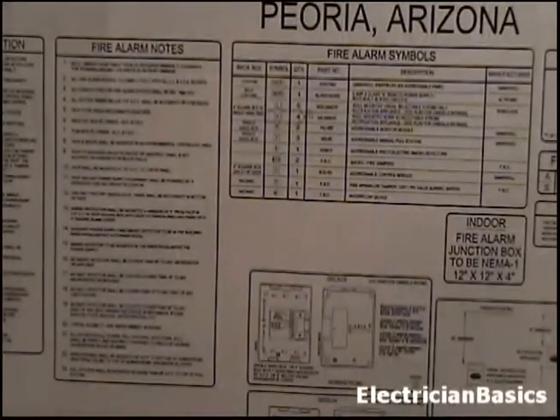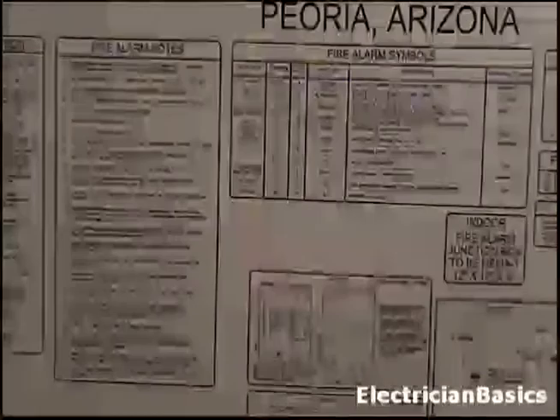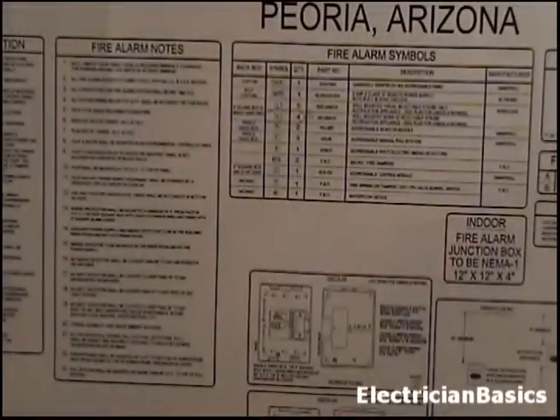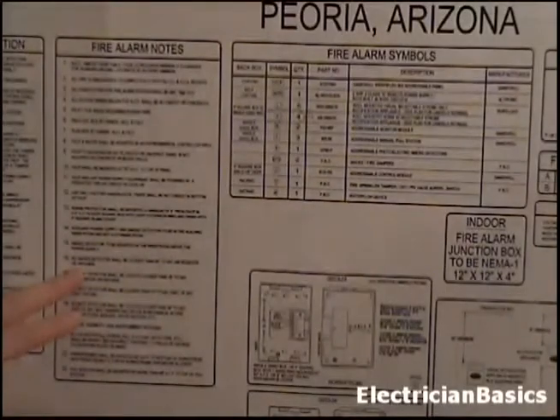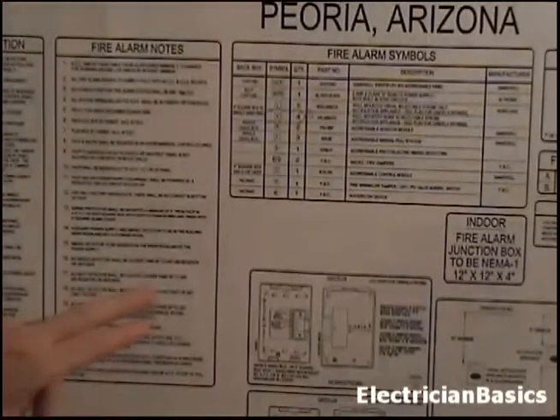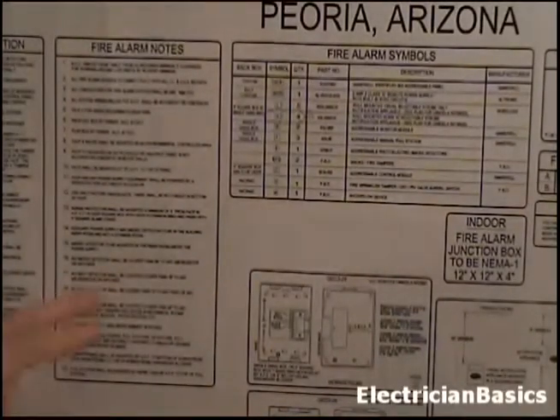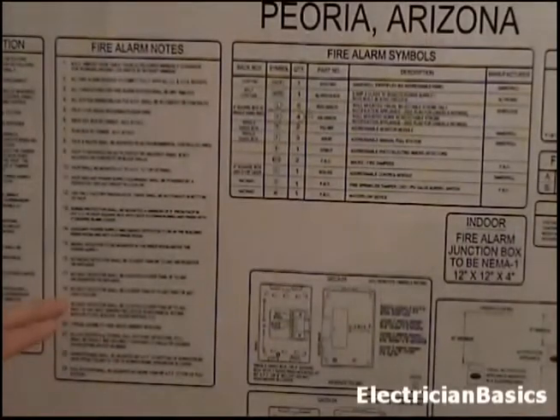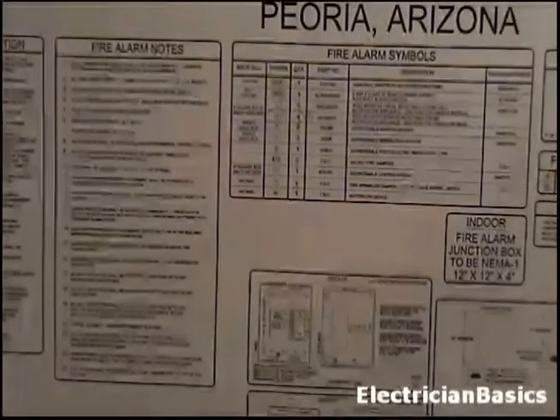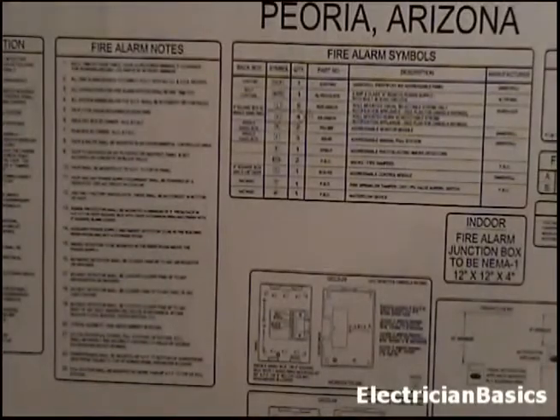Let's look at note 16 here. It says no smoke detector shall be closer than 36 inches to any air register or diffuser. And note 17, no heat detector shall be located closer than 18 inches to any air register or diffuser. And note 18, no heat detector shall be closer than 12 inches to any part of any light fixture. And let's look at note 19, no heat detector shall be located closer than 36 inches to any part of any heat generating device in mechanical rooms such as flues, boilers, water heaters, etc.